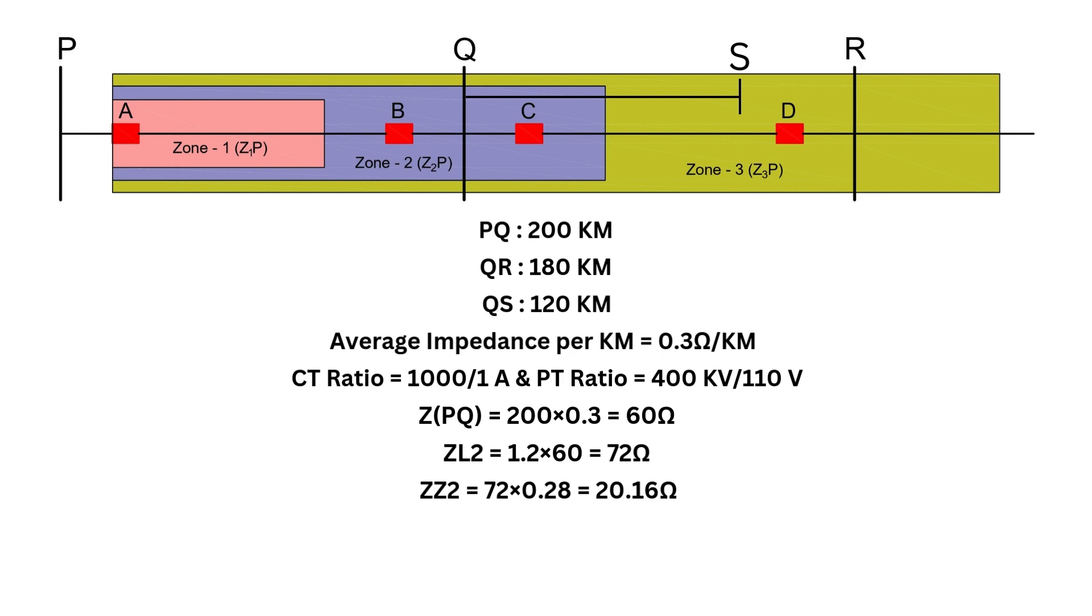And if the relay detects an impedance below this, it will trip the breaker after a 350 millisecond delay. This delay ensures that zone 1 at the remote end has time to act before zone 2 operates.